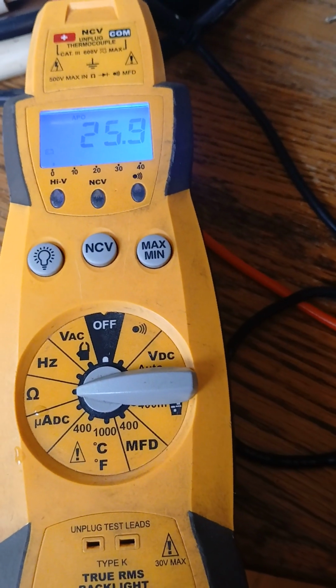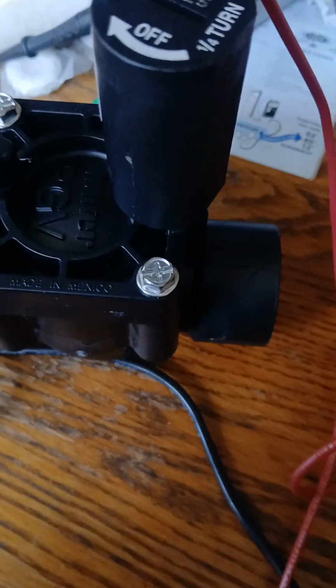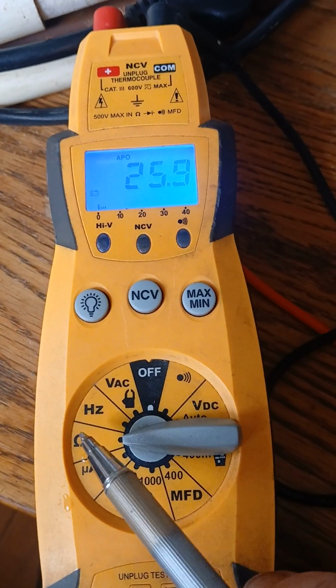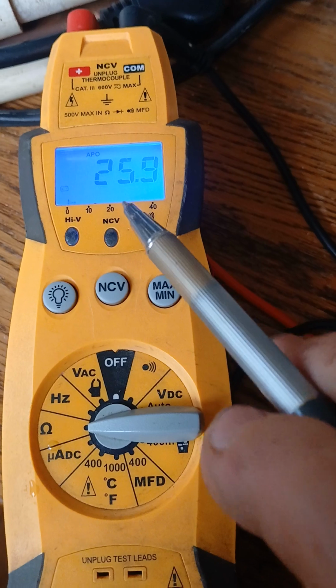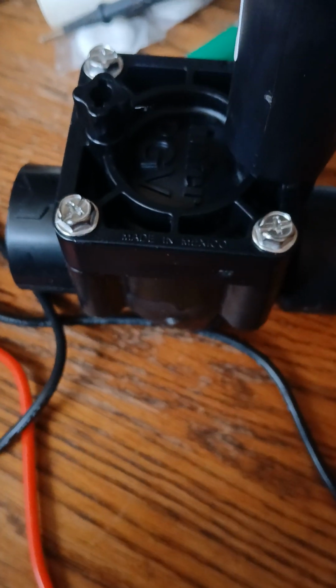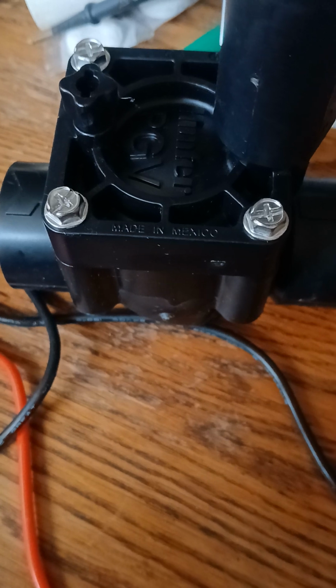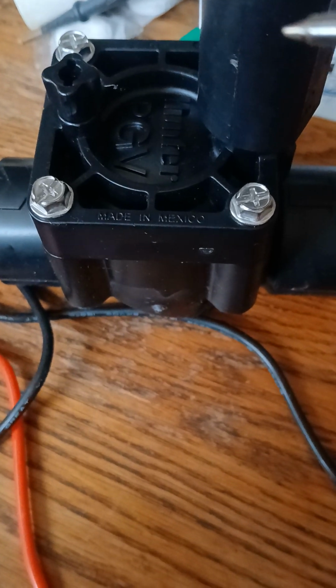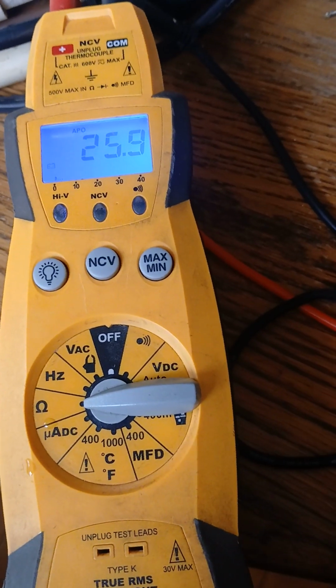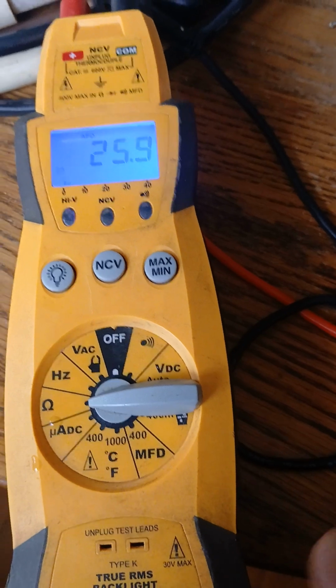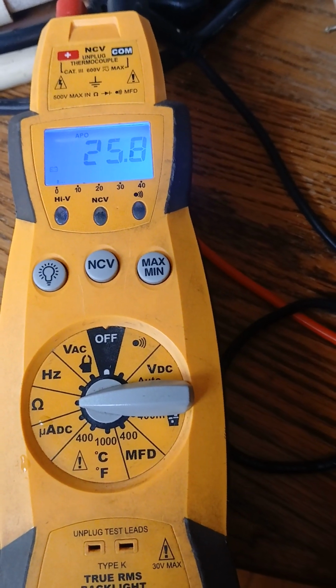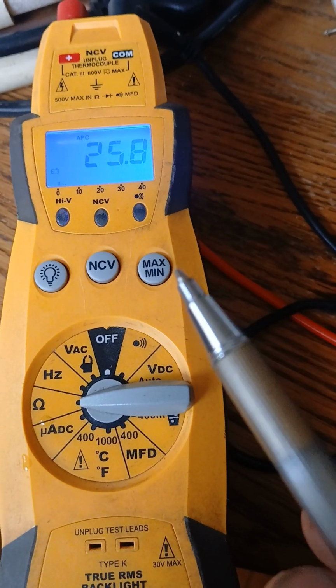Notwithstanding, 20 to 60 ohms may indicate a good solenoid or valve. In this case, we're set to the ohms position and reading 25.9 - this reads good. It was kind of a no-brainer since this is a new valve, but it's good to test something new to get an overall perspective, and you'd figure the new valve should be good. Anywhere from 20 to 60 ohms, we're at 25.9, so this valve reads good in the ohms position.